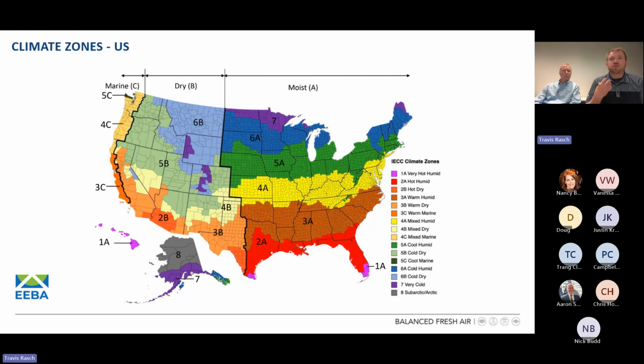Through the technologies we've got within that recovery core, the membrane or material it's made out of, as well as our ability to more effectively defrost or basically keep the recovery core from frosting, we were able to take that ERV technology and honestly move it all the way up, certainly into climate zone 6, and you might even get into part of climate zone 7 as well. There are different versions of ERVs that are more compatible with those colder climates as well. But again, we do see more and more ERVs being used throughout all the climate zones shown on this map. We do still have some diehards, particularly in the Minnesota market, using HRVs. God bless them. That's perfectly fine.